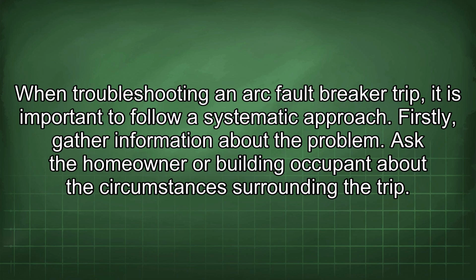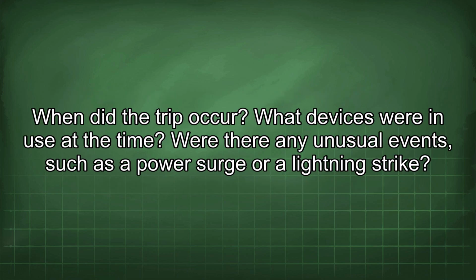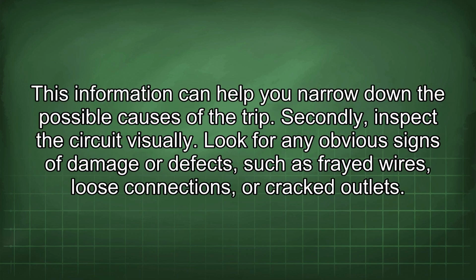Firstly, gather information about the problem. Ask the homeowner or building occupant about the circumstances surrounding the trip. When did the trip occur? What devices were in use at the time? Were there any unusual events, such as a power surge or a lightning strike? This information can help you narrow down the possible causes of the trip.